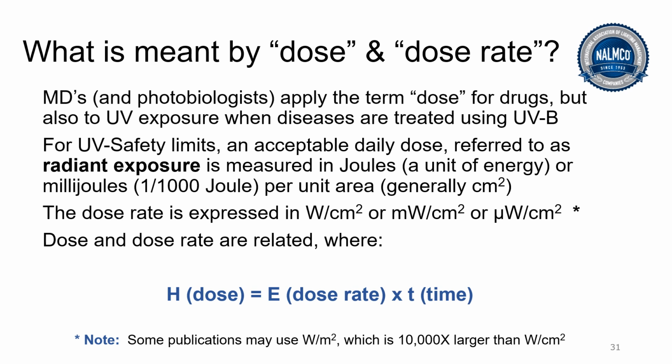As I said, the irradiance is often referred to as a dose rate, and the total accumulated radiant exposure, H, in terms of germicidal UV is right there.